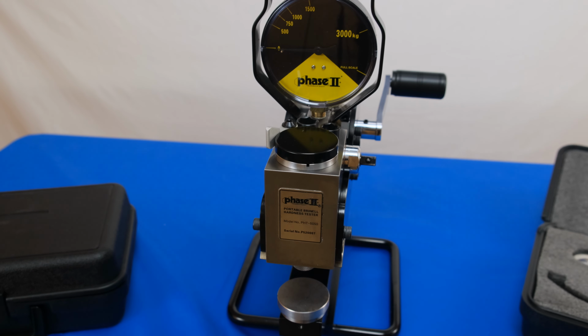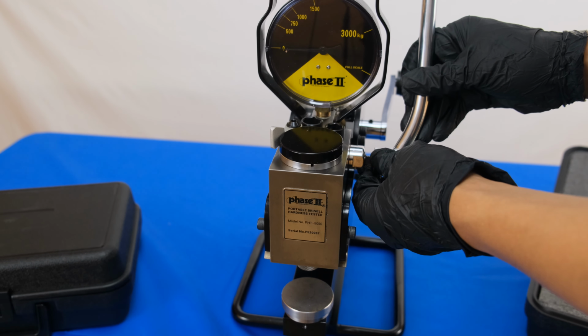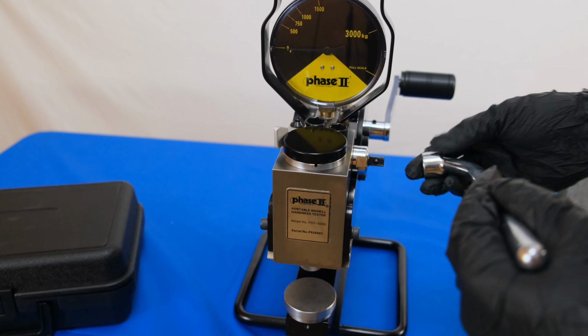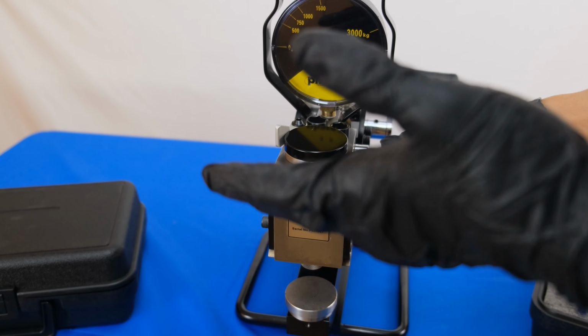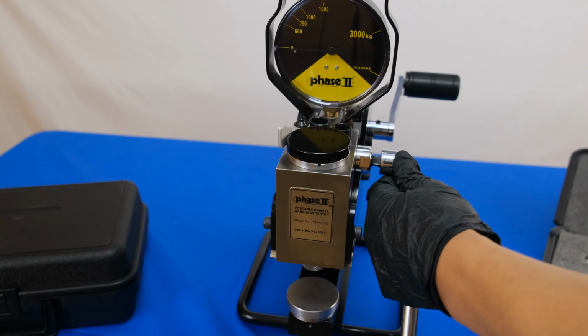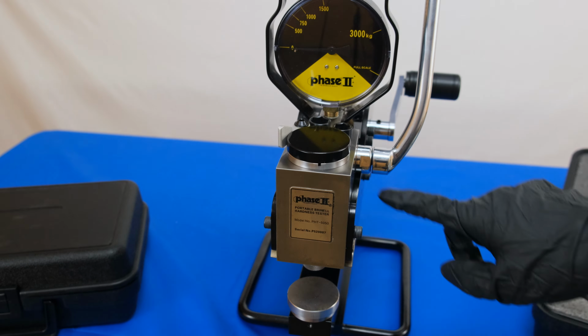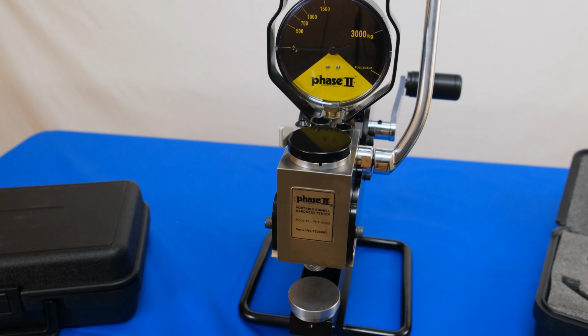Once the head unit has been attached, remove the handle from the kit. Ensure that the handle is affixed at the proper position. Note that improper mounting of the handle may make it challenging to pump the unit once testing begins. Once the PHT-5050 is assembled, you may begin testing.